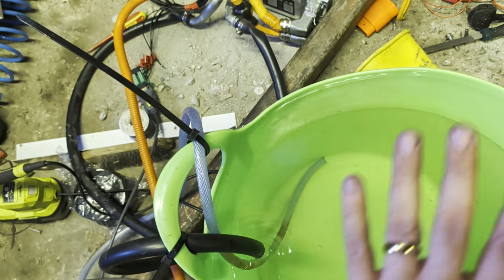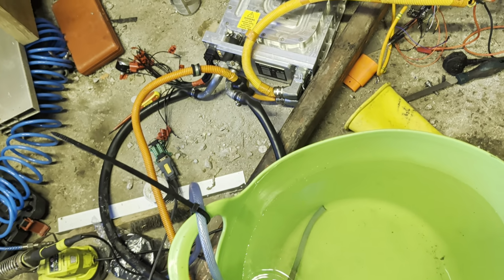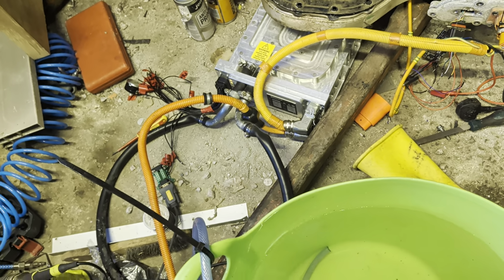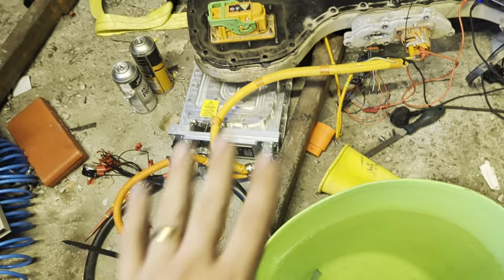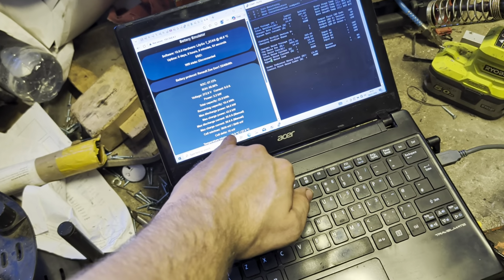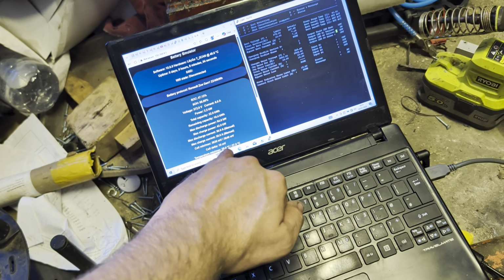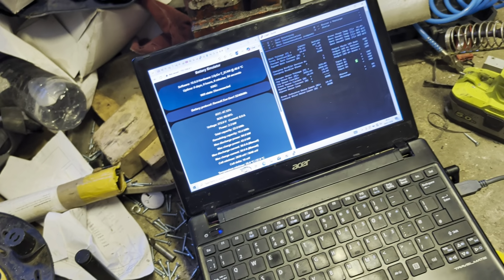It's a very small battery, only 22 kilowatt hours, and it's at 68% state of health, so only 18 kilowatt hours total capacity, and I'm only charging it up halfway. What I'm doing right now is babysitting the battery, making sure none of the voltages go out of whack. We've got a cell delta of 10 millivolts there, so we're very tight on our battery cells. I think that's the minimum it can report.